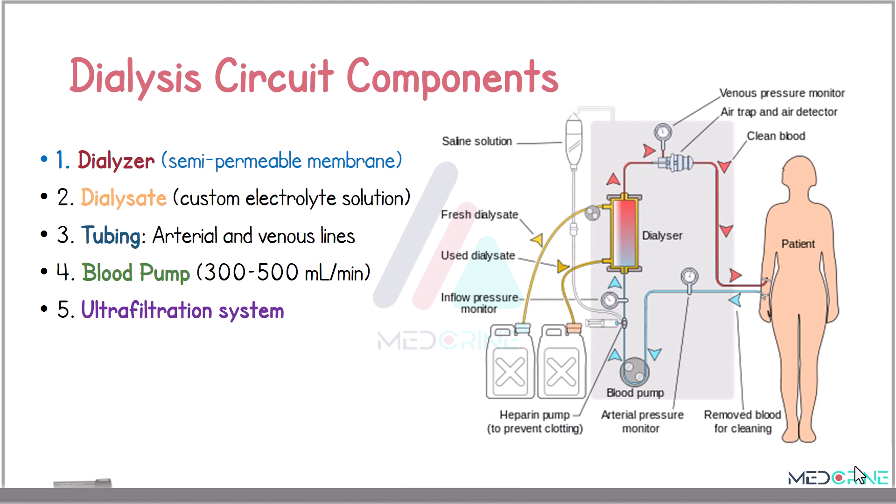In the dialysis circuit unit, we have a number of components including a dialyzer, which is a semi-permeable membrane that filters the blood; dialysate, which is a custom electrolyte solution that we use in dialysis; the tubings, which include arterial and venous lines; a blood pump that pumps approximately 300 to 500 ml of blood per minute; and an ultrafiltration system.